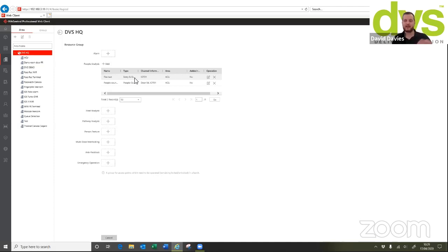And as long as they are clocking in and clocking out and not tailgating or holding the door, so you need anti-passback, you need to have read in and read out, because otherwise the muster list won't be accurate and you'll be sending fire people in for people, for ghosts effectively, that don't even exist.